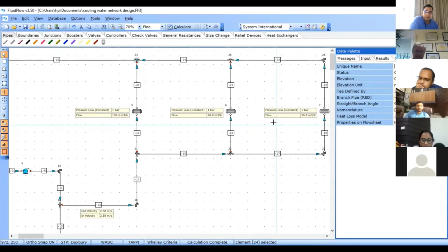The remedy part, right? In this case, we found out the problem is there because of pressure difference. Pressure differential is not the same in each of these three loops. Now the problem you know, so what is the solution? We should throttle the cooling water flow to the first one.